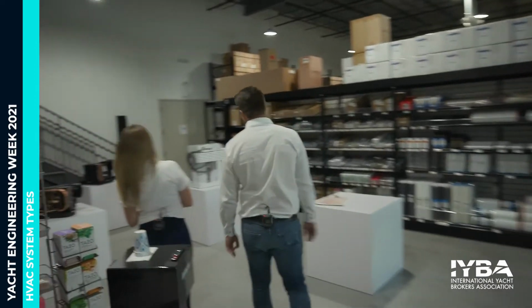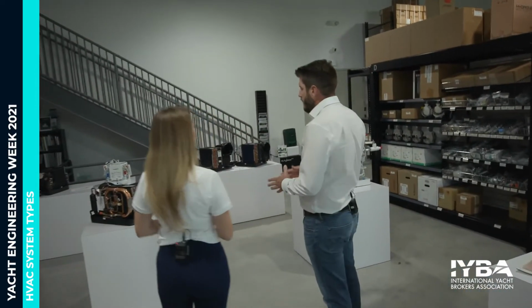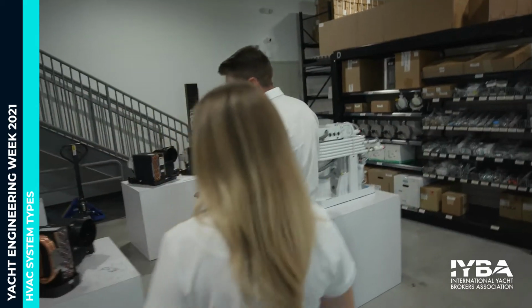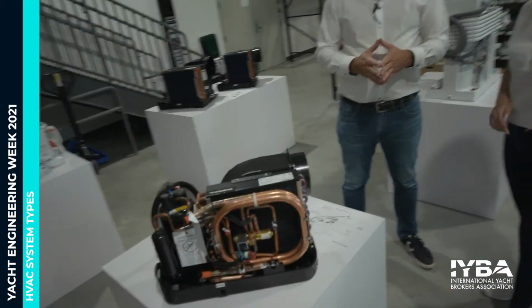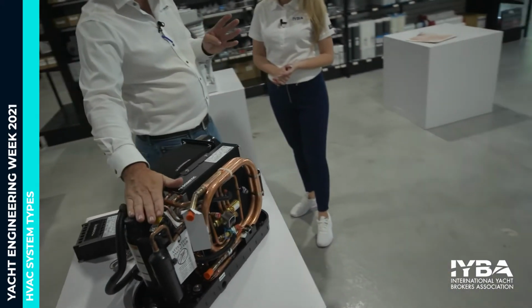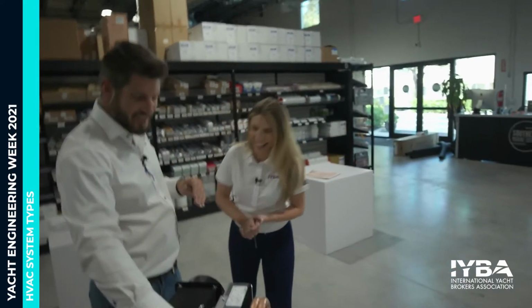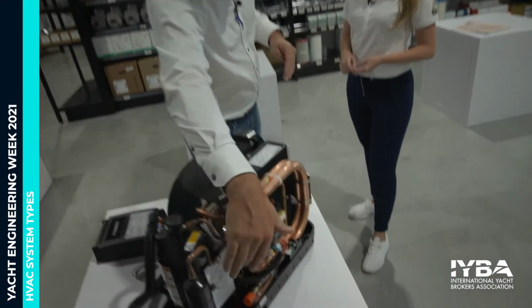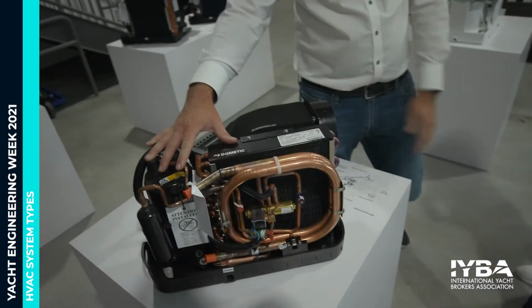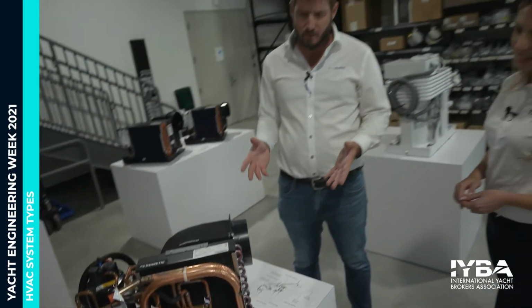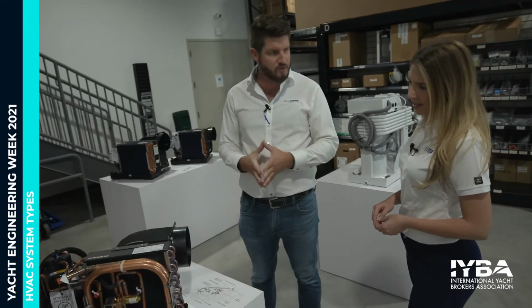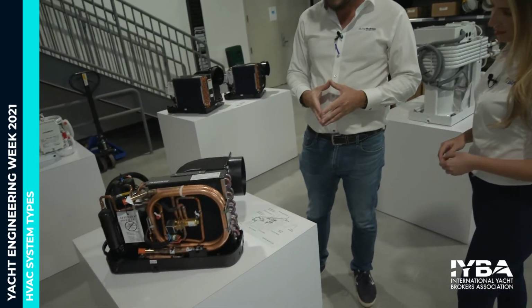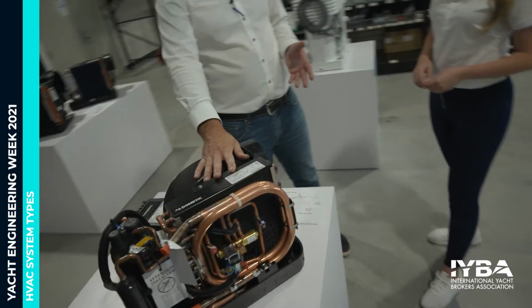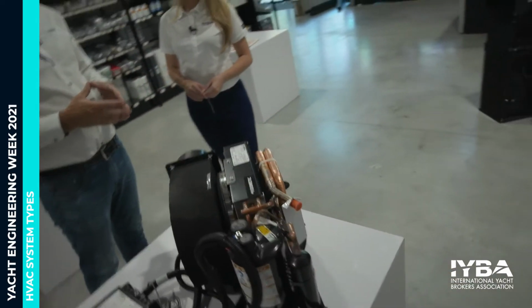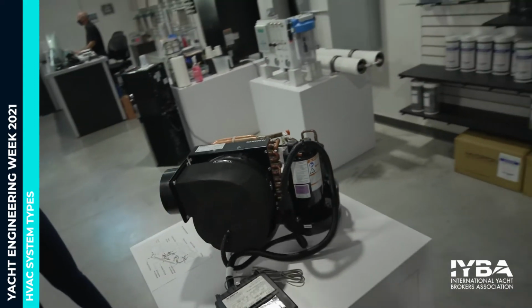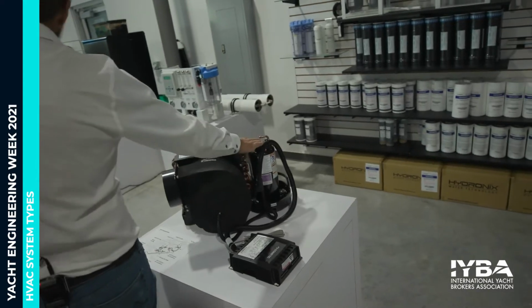So there's three different types of marine AC systems. The first is a self-contained unit, for your smaller boats, 30 to 50 feet. A self-contained unit has all four of those major components. Do you remember what they are? No. Okay: compressor, condenser, evaporator, metering device. That's right, so everything is self-contained. These are great because they're easier to install—you can have your do-it-yourselfers occasionally install those. But there are some compromises. They do make more noise because they're located in the cooled or conditioned space, so it could be under the master bedroom, for example, and it's going to make a bit more noise because the compressor is inside the cabin.